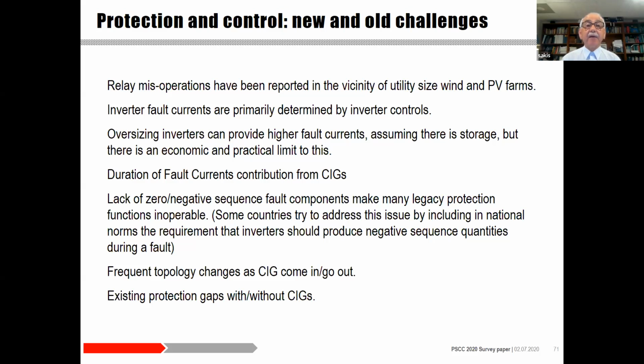The duration of fault currents from converter interfaced generation is relatively short. Another important issue is that inverters do not generate substantial quantities of zero and negative sequence currents, and many protection systems depend on the existence of zero and negative sequence currents for the detection of the fault and appropriate action. A lot of countries have approached this problem by simply requiring inverter manufacturers to modify the control so that during a fault, the inverters can provide negative and sometimes zero sequence currents to facilitate the operation of the protection. However, this is not a good approach. We're engineers. We really need to have better approaches to deal with this new problem.